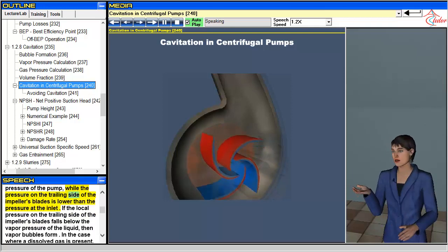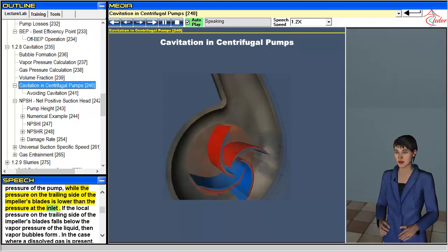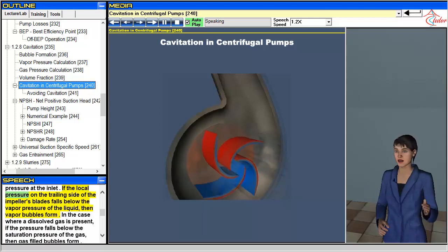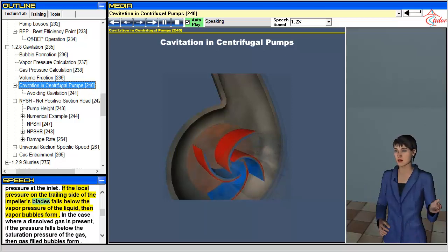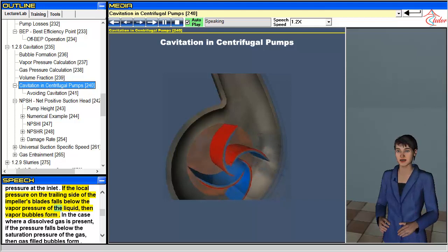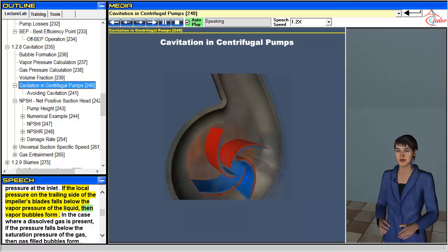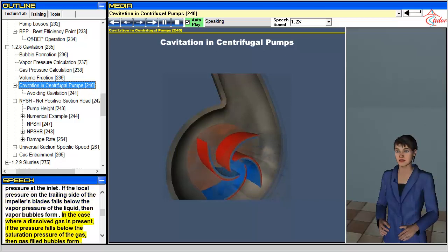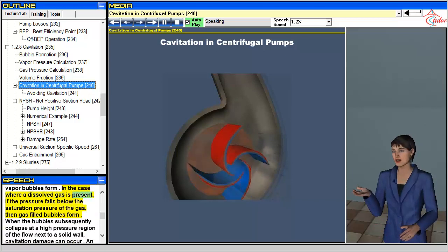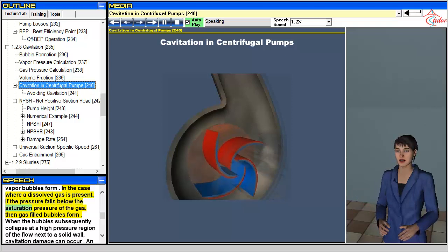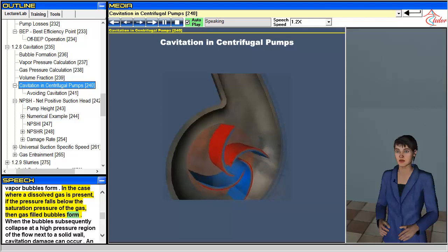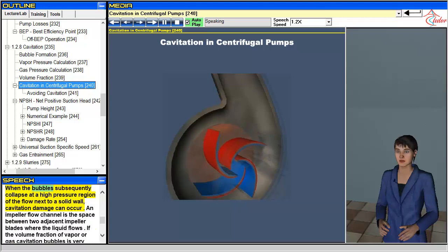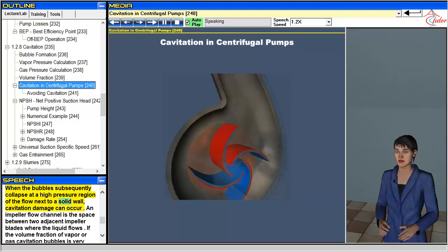The pressure on the trailing side of the impeller's blades is lower than the pressure at the inlet. If the local pressure on the trailing side falls below the vapor pressure of the liquid, then vapor bubbles form. In the case where a dissolved gas is present, if the pressure falls below the saturation pressure of the gas, then gas-filled bubbles form. When the bubbles subsequently collapse at a high-pressure region of the flow next to a solid wall, cavitation damage can occur.